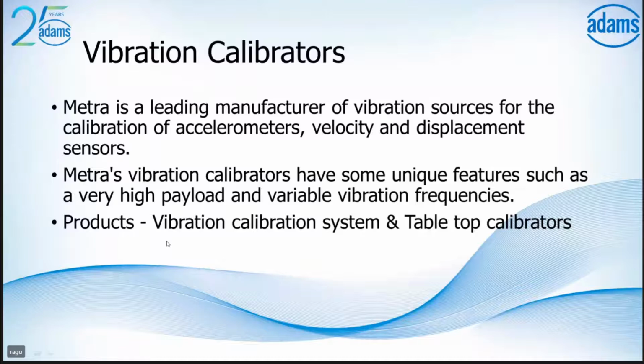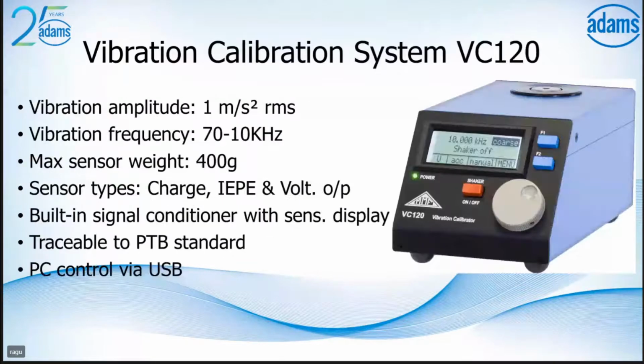So this is the vibration calibration system from Metra. It is small, portable, and like a tabletop. You can put it on the tabletop and do the calibration. This small system allows you to calibrate your sensor completely, from the frequency 70 Hz to 10 kilohertz, and the amplitude is 1 meter per second square RMS. At the rear end of the calibrator, you have a BNC connector. You can mount the sensor over here. Another advantage of using Metra is you can mount sensors as heavy as 400 grams on the calibration system.